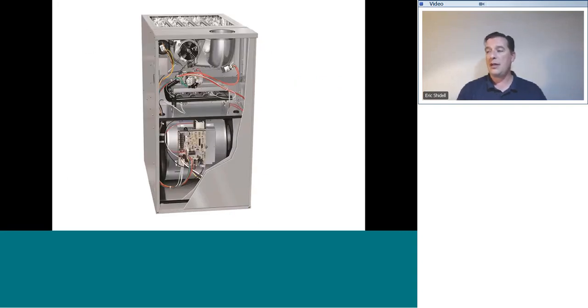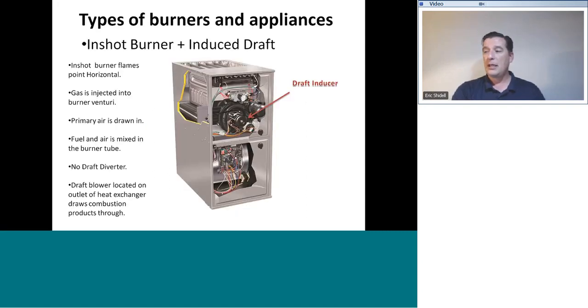Here's a closer-up shot of that same picture. Now, that was the case for an 80% AFUE furnace. Once we get above 90%, things are a little bit different. 90% furnaces will condense water inside the furnace on purpose to get that extra energy efficiency up.